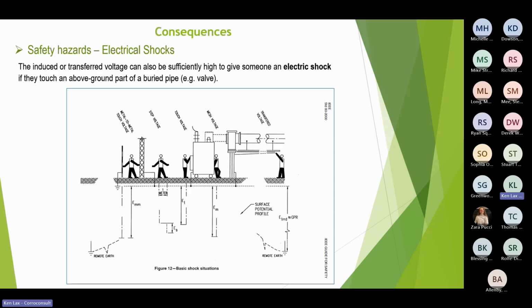And the other thing is, of course, if you have an above ground valve that you need to adjust, you could easily have a voltage difference there, which could give you an electric shock. When we think that that might happen, we do put a special ground mat there, and all that does is level up the seesaw so it's equipotential, all at the same potential, so there's no slope. So the person standing there won't actually get an electric shock just from being there.